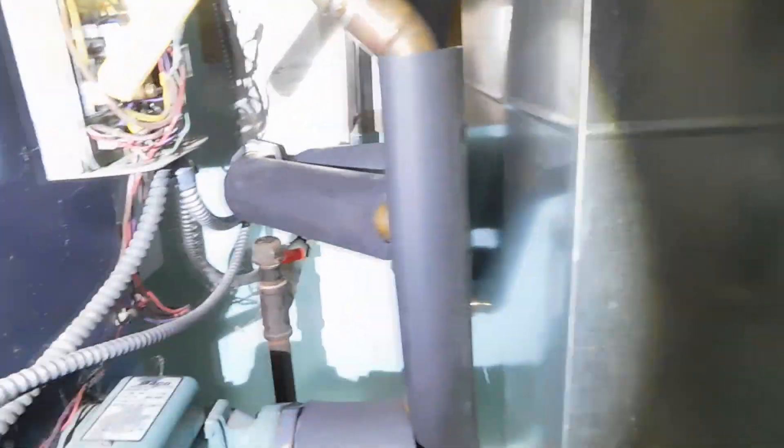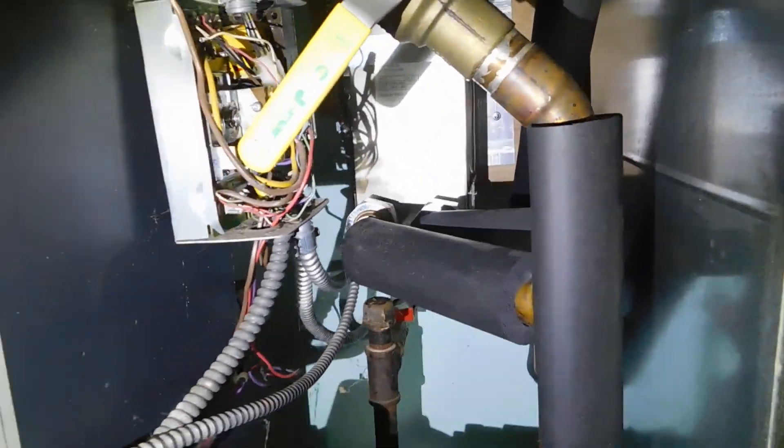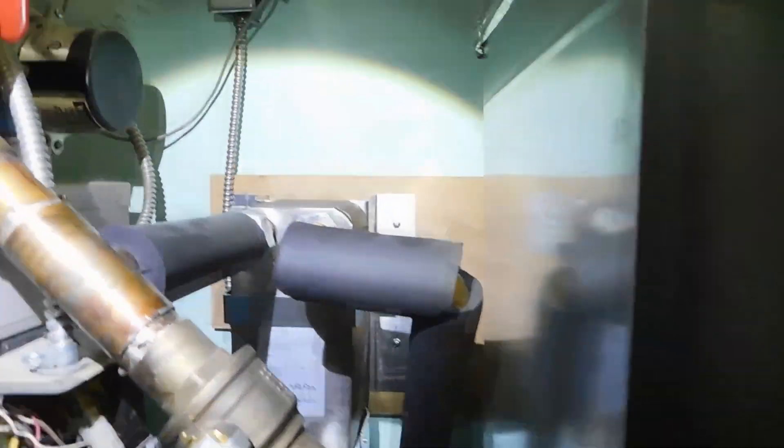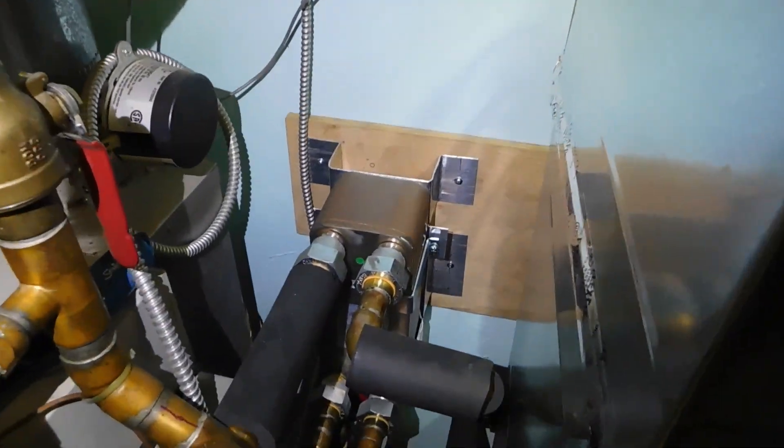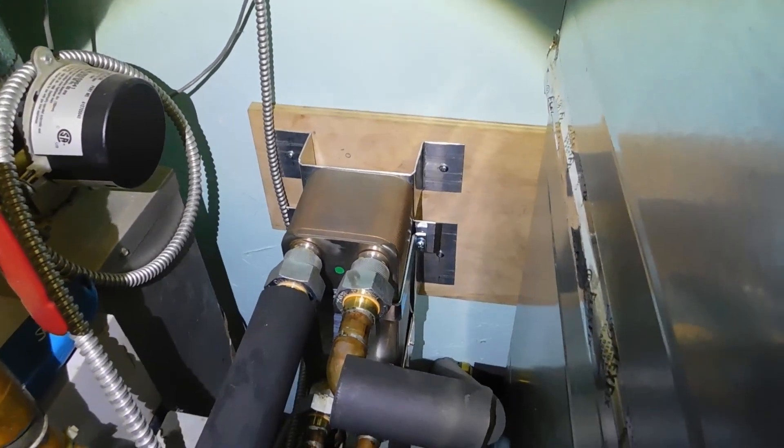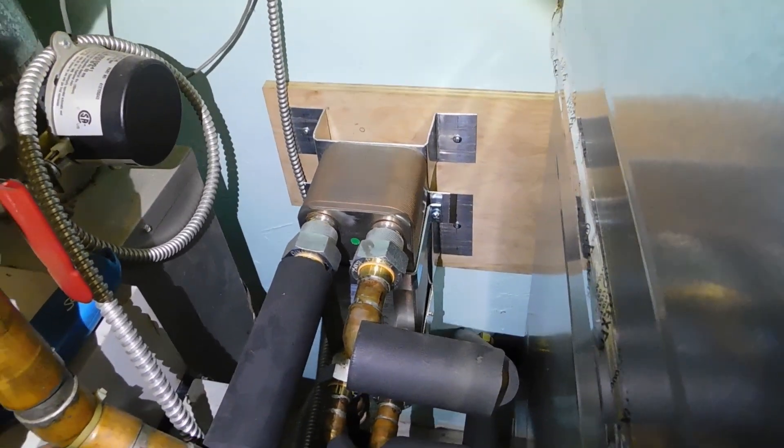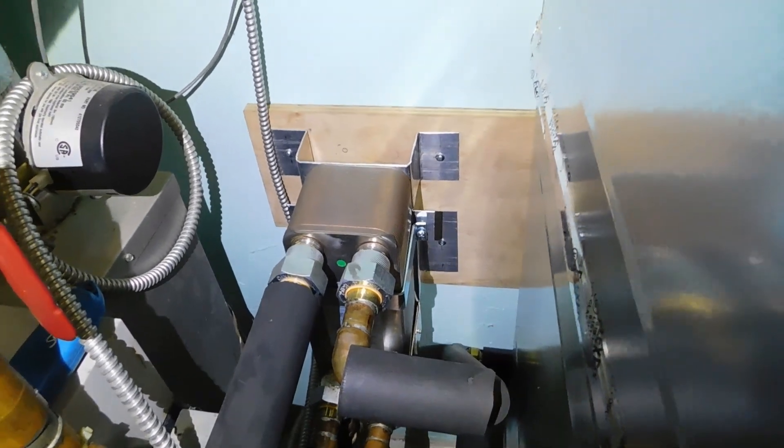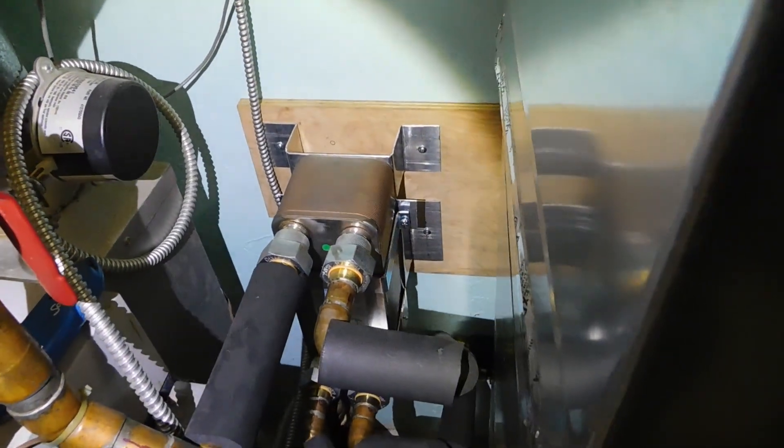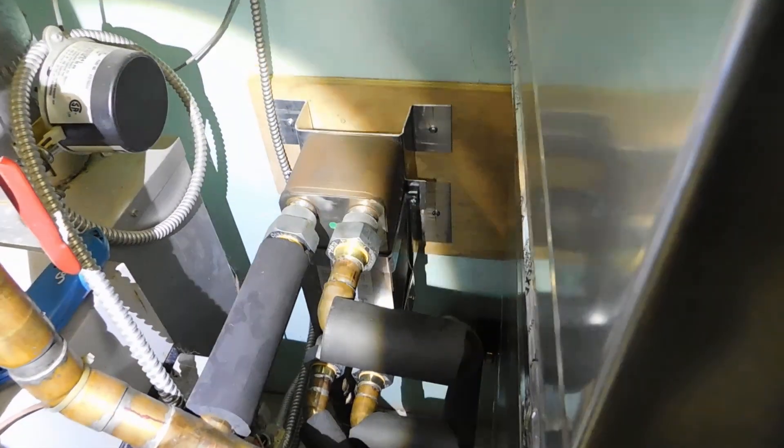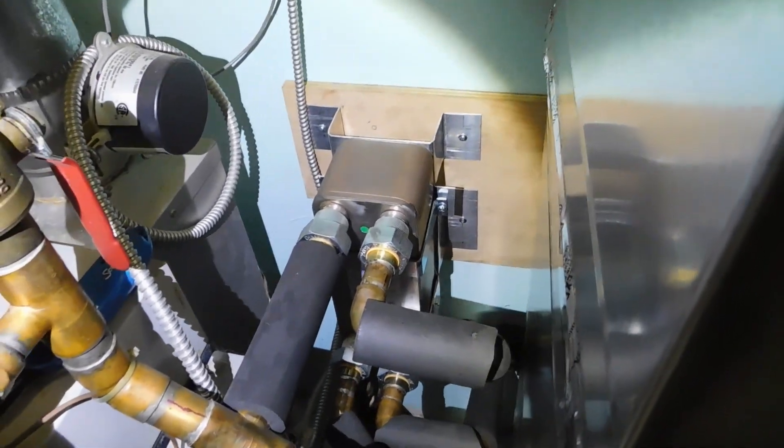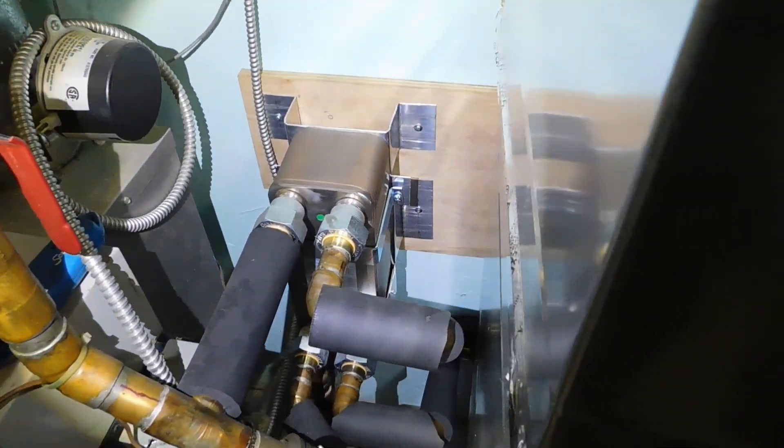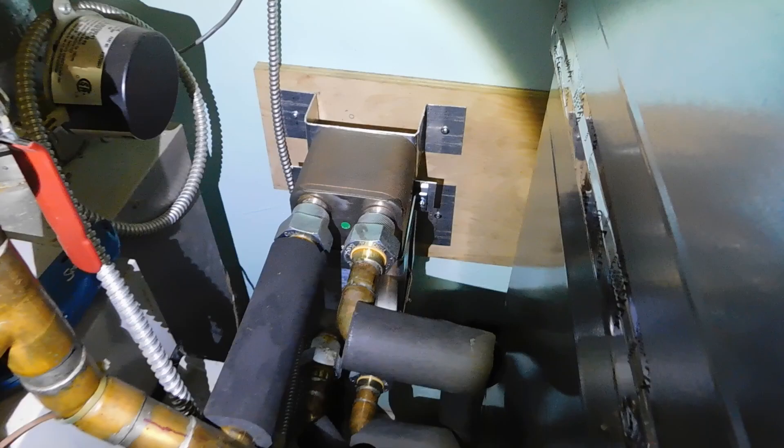So supply and return around this old furnace, or the forced air furnace, then we come down to the plate exchanger. This is where the business happens. We got a 40-plate heat exchanger. So you've got metal plates stacked on top of each other, and then water from the house boiler system goes through one stack of plates, and they alternate, so then the water from the outdoor wood boiler goes through the other plates.